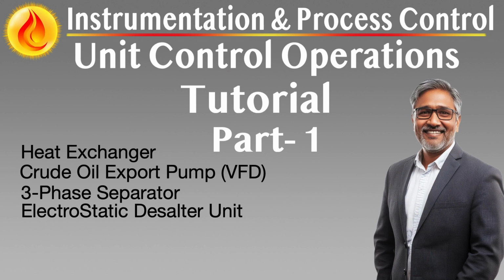In a typical configuration, the outer loop controls process fluid temperature, while the inner loop rapidly responds to utility flow changes. Advances in sensor technology have improved measurement resolution and response time, enabling more aggressive loop tuning and tighter temperature regulation. Additionally, equal percentage control valves, selected for their linearizing effect, are now often coupled with smart positioners that provide diagnostic feedback and ensure precise valve travel.